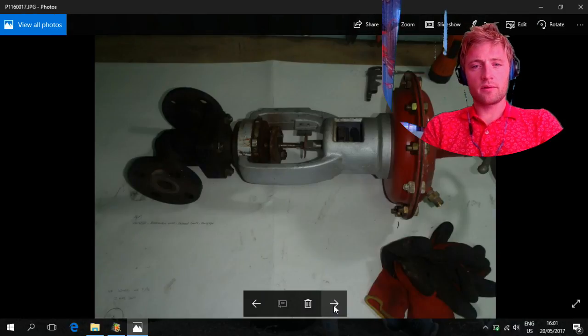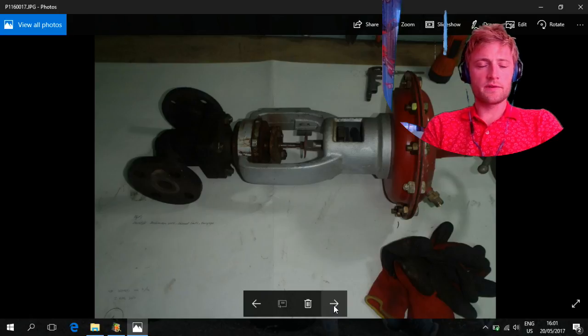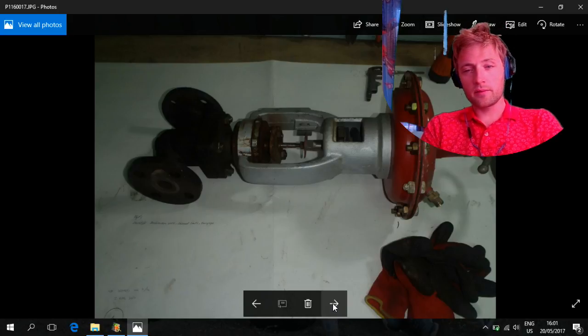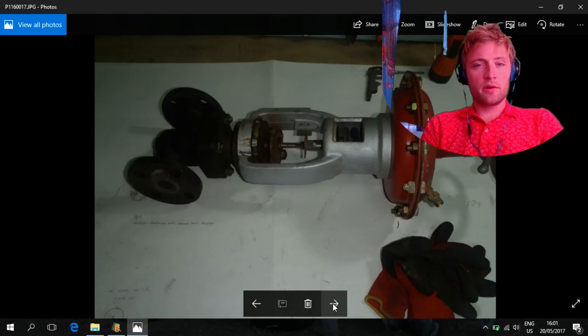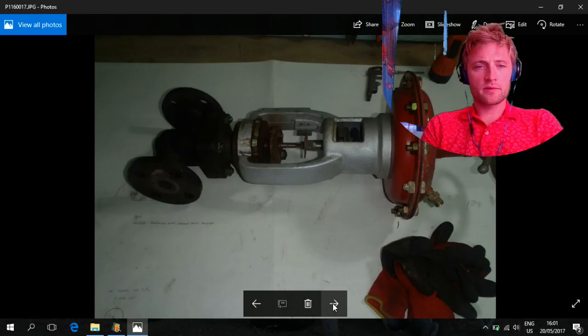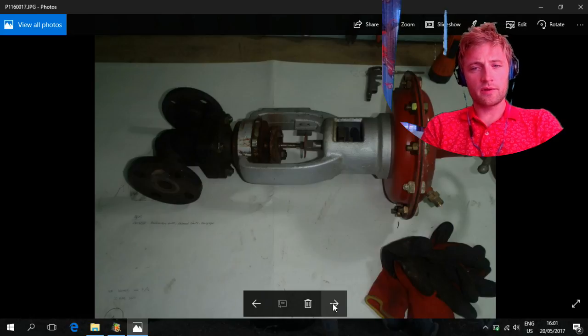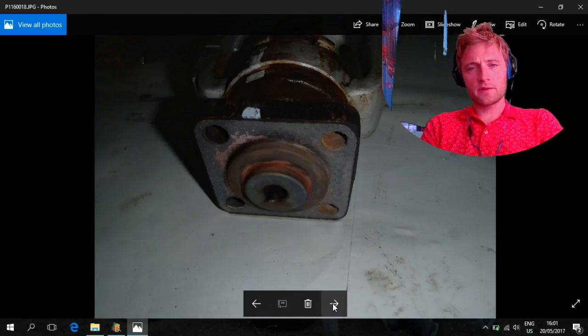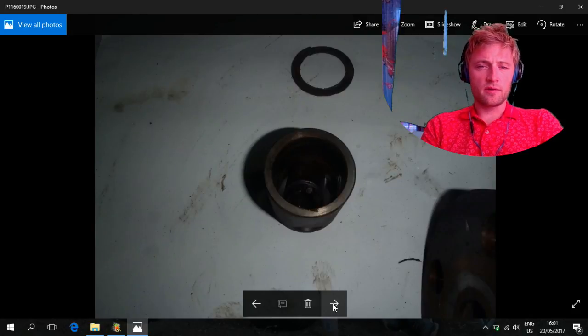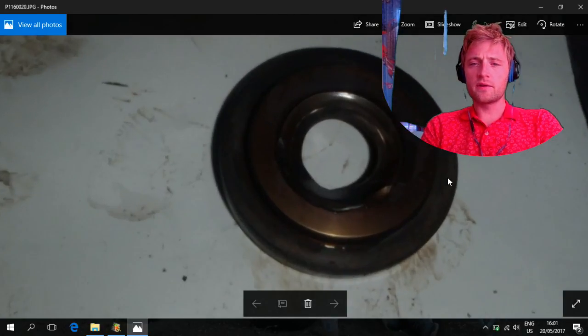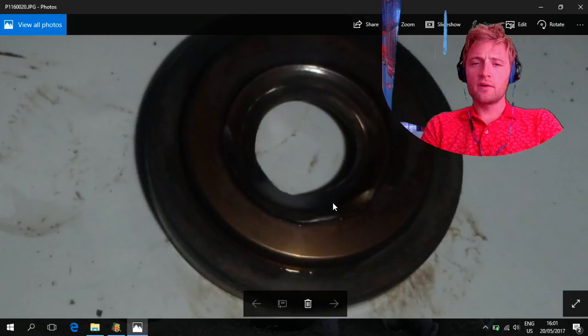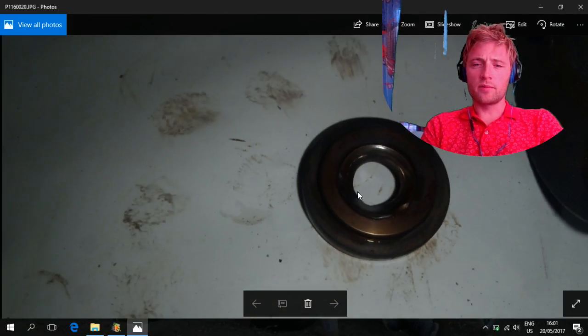Next we have this valve here. This is the steam regulating valve for the heater. In my service on that ship, we removed two of these valves for the steam heaters and I found that the seat and the piston inside were damaged.